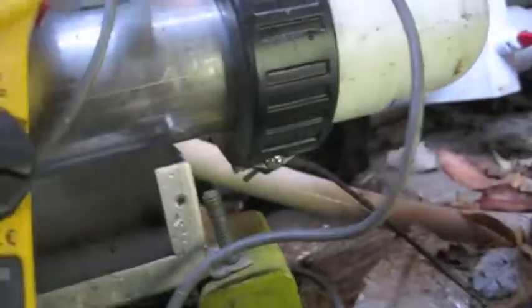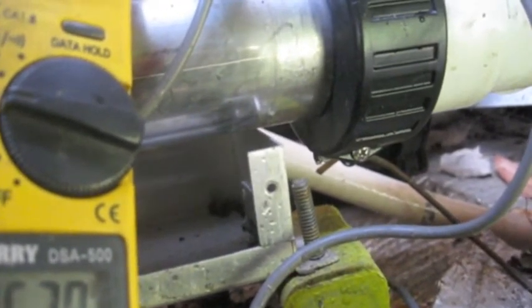And this is what happens when you've got 300 volts going to a breaker and it's not making a good connection in the back of the breaker. It happens pretty fast, so just pay attention.